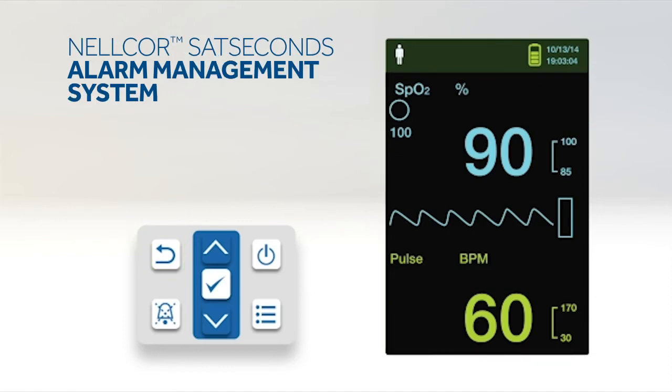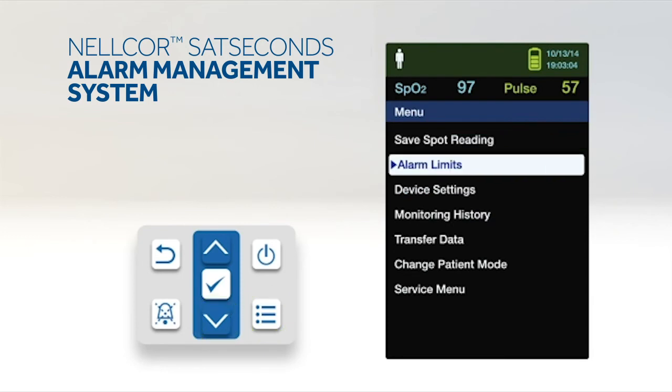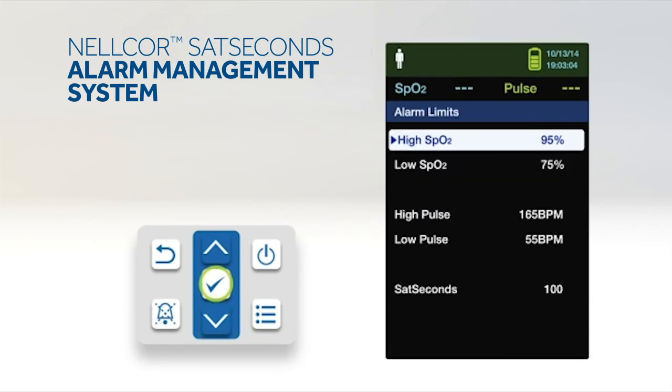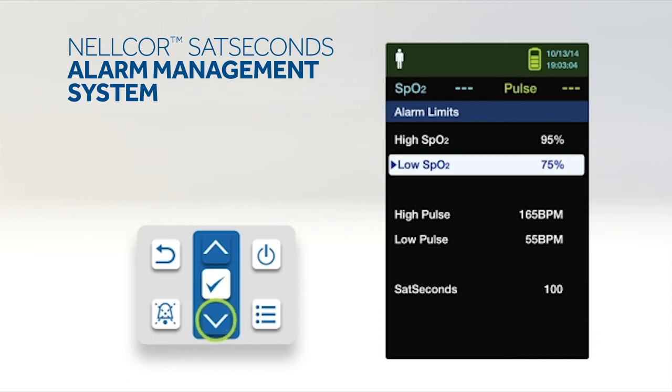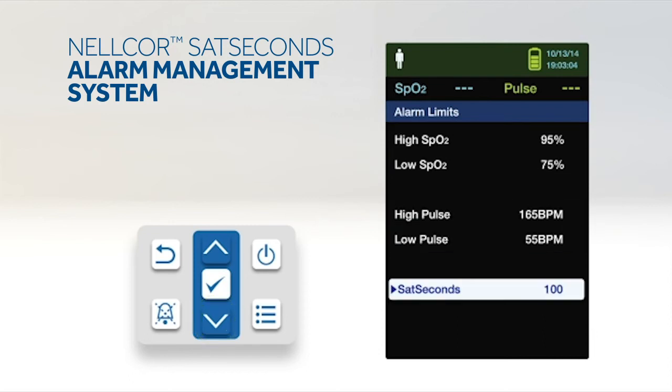To set Nellcor SatSeconds, press the menu button. Press the down button to highlight the alarm limits menu item and press OK to select. On the alarm limits menu, press the down button to highlight SatSeconds.